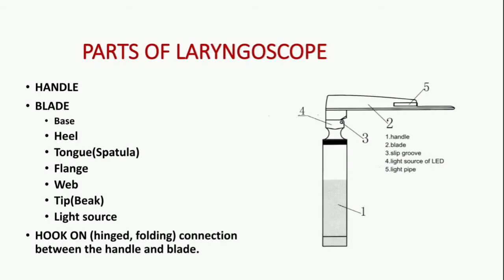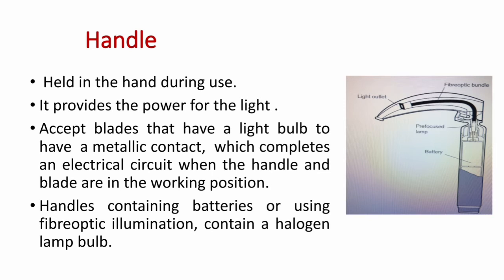The laryngoscope has different parts: the handle, the blade, and the hook. The handle is held in the hand during use and provides power for the light. It accepts blades that have a light bulb and a metallic contact which completes an electrical circuit when the handle and blade are in the working position. Handles containing batteries or using fiber optic illumination contain a halogen lamp bulb.